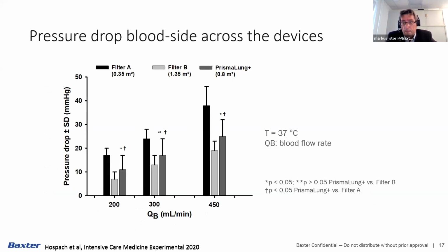I mentioned that blood flow resistance in such a setting is very important, and we measured the pressure drop on the blood side for the different devices. We see that the pressure drop was largest for the smallest device, the 0.35 square meter filter, and lowest for the largest device, suggesting that the difference is likely driven by the membrane area and the blood volume in the device. But the pressure drop values across all three devices were relatively low, with levels of up to 25 millimeter mercury with PRISMALUNG Plus at the blood flow rate of 450 mL per minute.